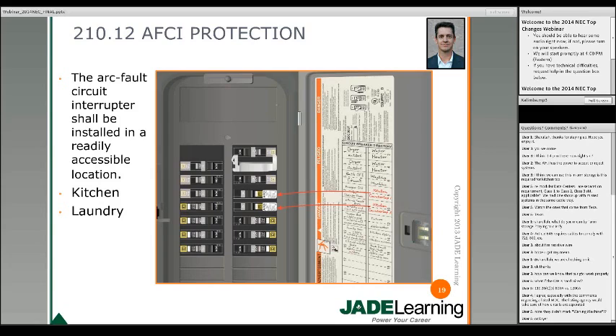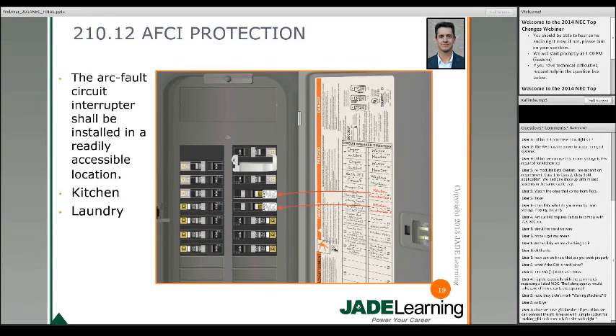It's going to take some thought on the part of the inspector who has to make a judgment call at final inspection, sometimes without the appliances present. You'll have to consider what's going to happen once they put the washing machine in. To answer directly: yes, the receptacle outlet for a washing machine in the laundry and a refrigerator in the kitchen will have to be AFCI protected — everything in the kitchen, everything in the laundry. It's not relative to whether a sink is present. AFCI and GFCI both apply to kitchen and laundry for 125-volt single-phase 15-20 amp receptacles.